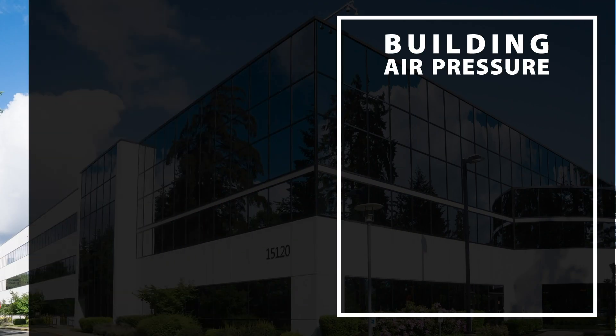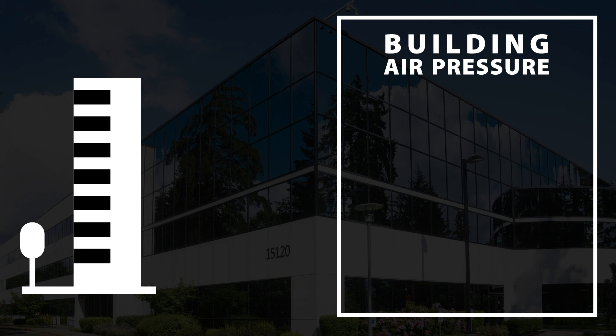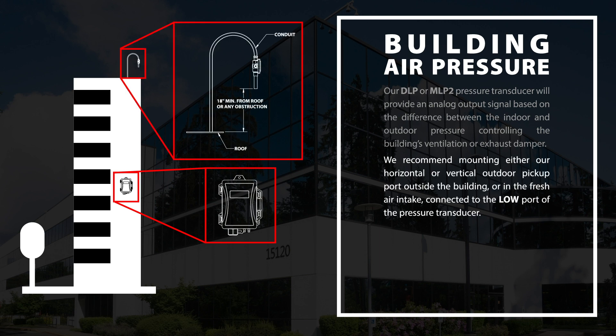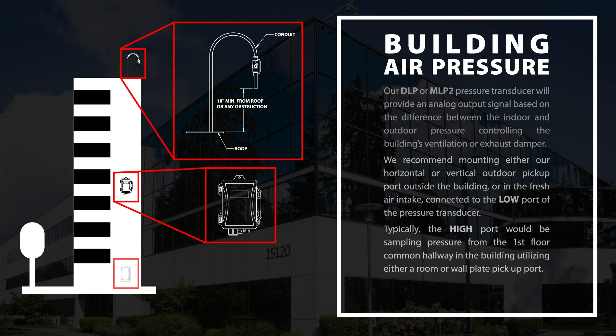Whether the building requires a slightly positive or negative pressure, you will need an outdoor and indoor pressure sample reference. Our DLP or MLP2 pressure transducer will provide an analog output signal based on the difference between the indoor and outdoor pressure, controlling the building's ventilation or exhaust damper. We recommend mounting either our horizontal or vertical outdoor pickup port outside the building or in the fresh air intake, connected to the low port of the pressure transducer. Typically, the high port would be sampling pressure from the first floor common hallway in the building, utilizing either a room or wall plate pickup port.